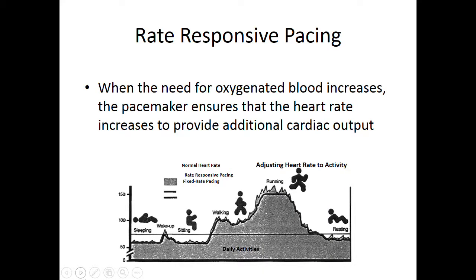Another major advance is what we call rate responsive pacing. The old pacemakers, you just set them at a single rate. You set them at 60 or 70 and that's all they would do. The newer devices have a sensor in them. So they try to mimic more closely what Mother Nature would do, because if all of us start walking or exercising or running, our heart rate should go up. And the pacemaker will actually sense that and adjust your heart rate up to what would be more closely what Mother Nature would give us to start with. So it was nice because, particularly for younger patients, we could have the pacemaker adjust to the activity level of the patient.